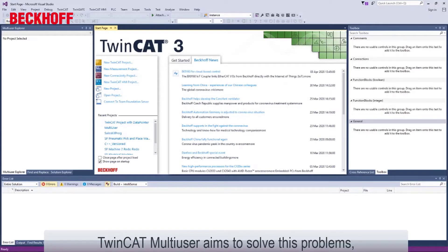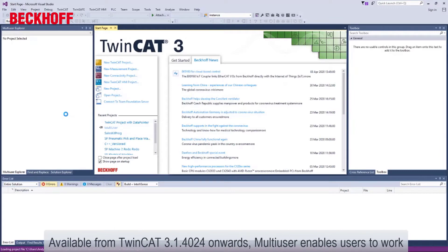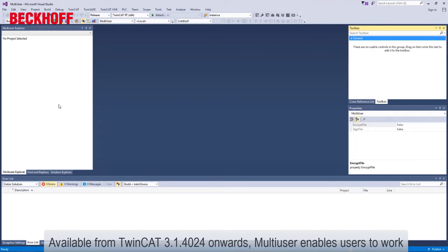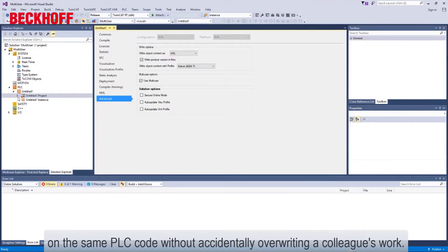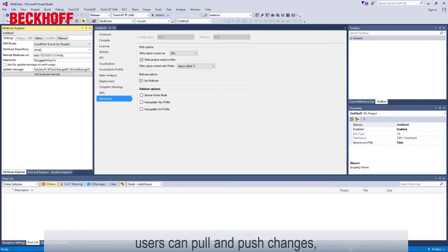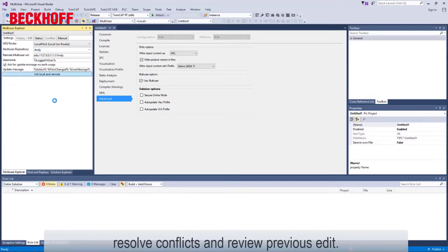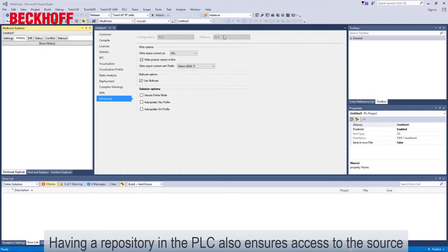TwinCAT multi-user aims to solve these problems by incorporating version control into the project itself. Available from TwinCAT 3.1.4024 onwards, multi-user enables users to work on the same PLC code without accidentally overwriting a colleague's work. By creating a repository in either a remote server or the PLC itself, users can pull and push changes, resolve conflicts, and review previous edits. Having a repository in the PLC also ensures access to the source control system.